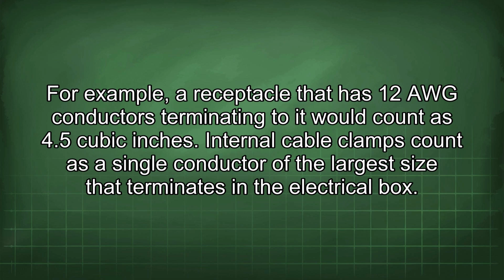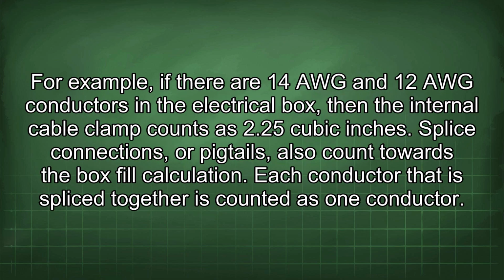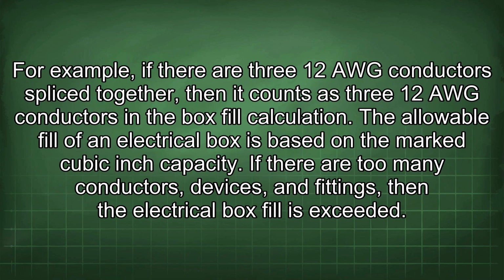Internal cable clamps count as a single conductor of the largest size that terminates in the electrical box. For example, if there are 14 AWG and 12 AWG conductors in the electrical box, then the internal cable clamp counts as 2.25 cubic inches. Splice connections, or pigtails, also count towards the box fill calculation. Each conductor that is spliced together is counted as one conductor. For example, if there are 3 12 AWG conductors spliced together, then it counts as 3 12 AWG conductors in the box fill calculation. The allowable fill of an electrical box is based on the marked cubic inch capacity.